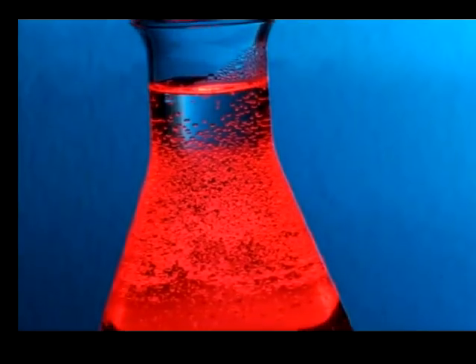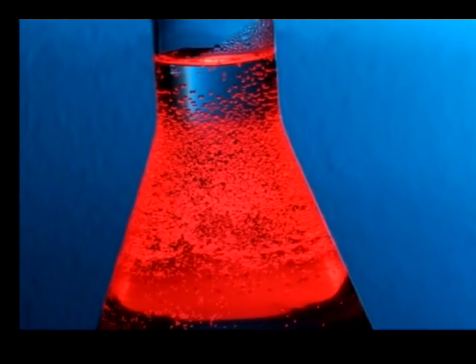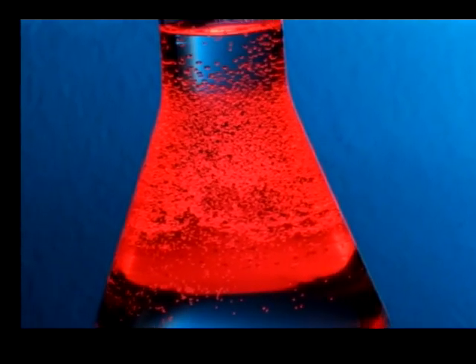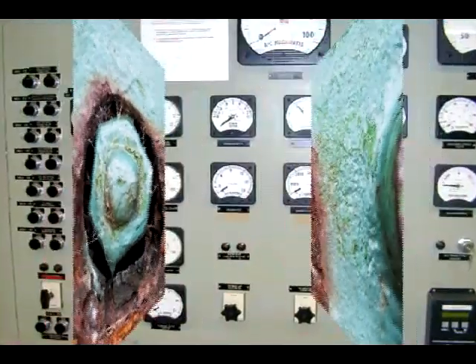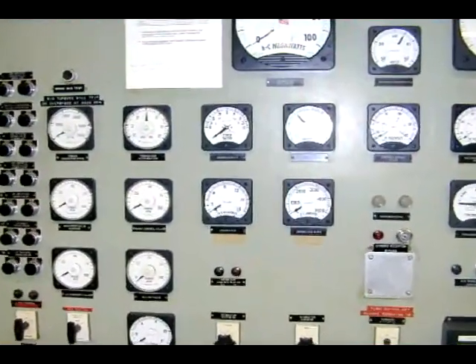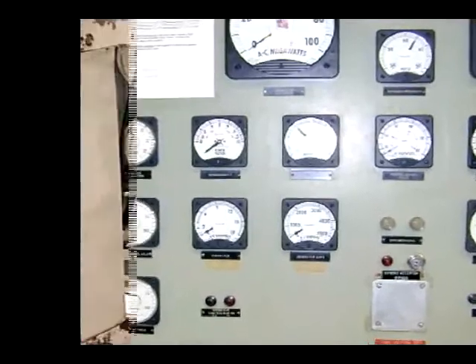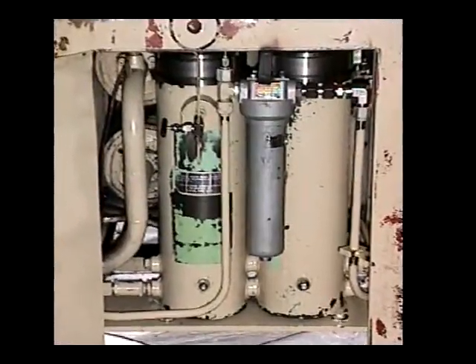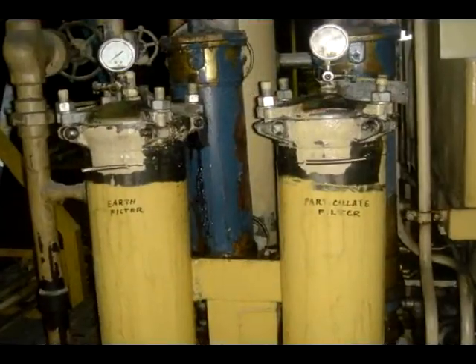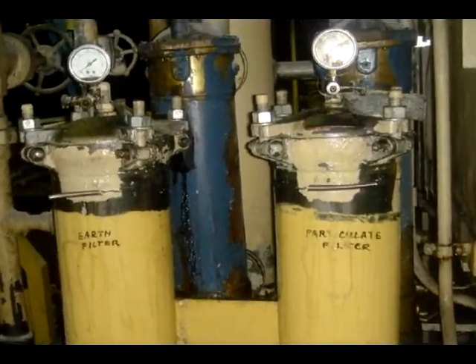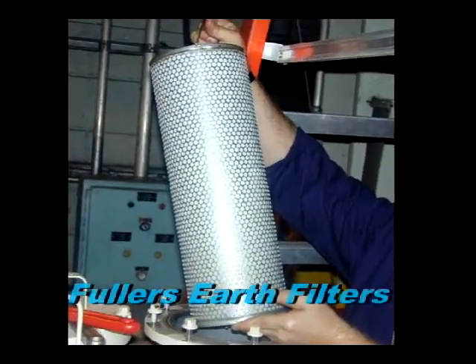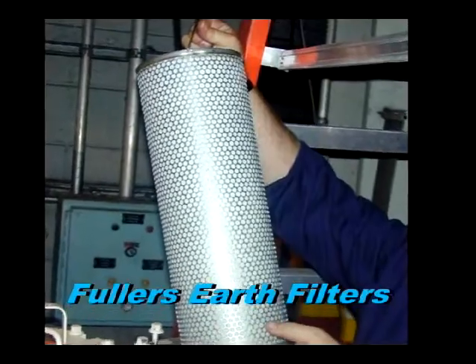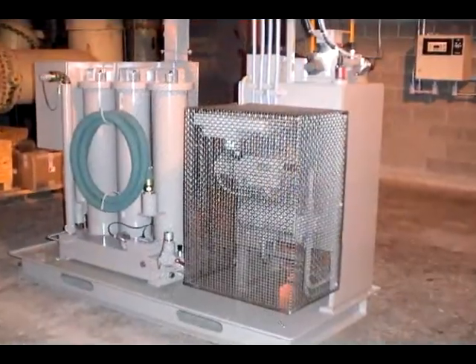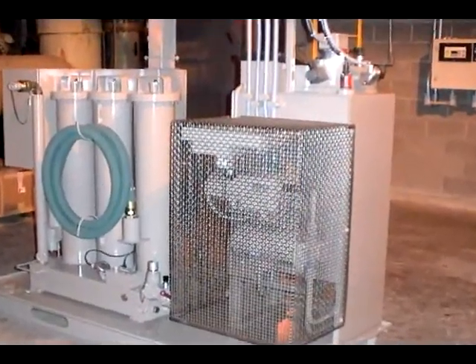First, the phosphate ester fluids naturally create aggressive acids, such as phosphoric acids. If these acids are left unchecked, severe corrosion of the system components could occur, resulting in a forced outage on the unit. In order to control the development of the acids, acid control filters were added to the hydraulic power units. Initially, Fuller's earth filters were used to control the FRF acidity. These filters are still in wide use throughout the industry.